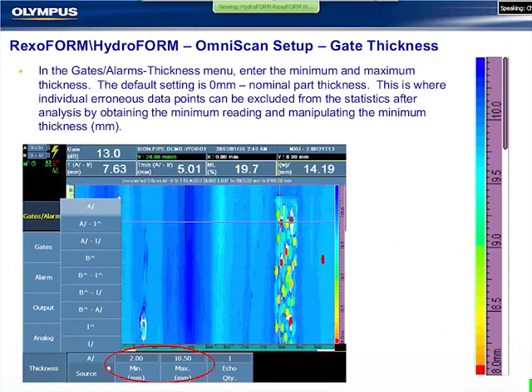The gate thickness is something that the weld inspectors typically don't ever have a reason to use. So those of you who are new to corrosion mapping but maybe an expert on the OmniScan, it's a part of the program that might be new to you. But under the gate alarms menu, under thickness, we're going to configure how we want the A-scan to read the thickness reading. And as you see here, typical of a conventional flaw detector or an automated conventional system, all of the gate logic is available here.